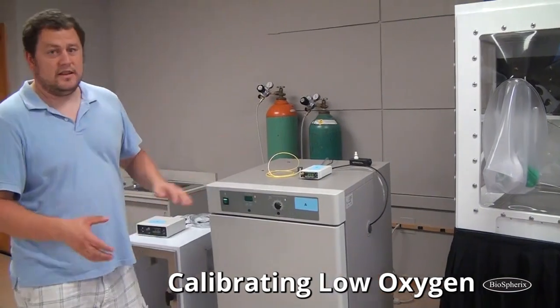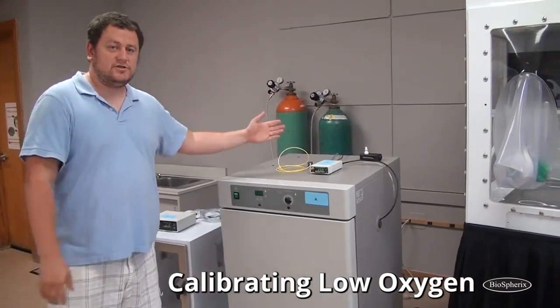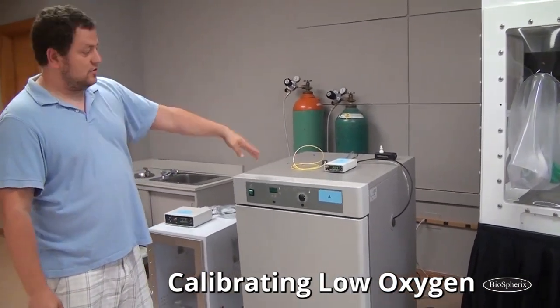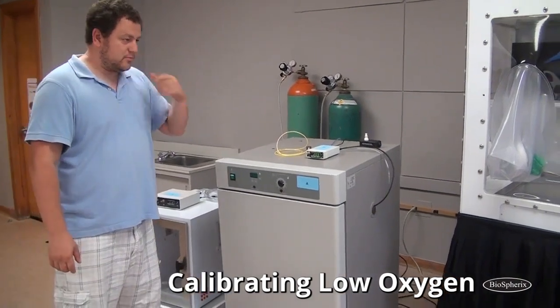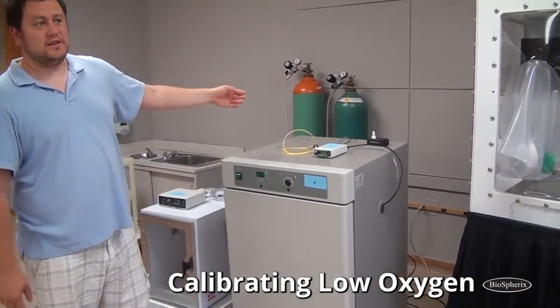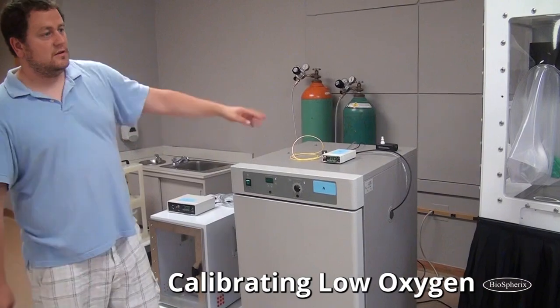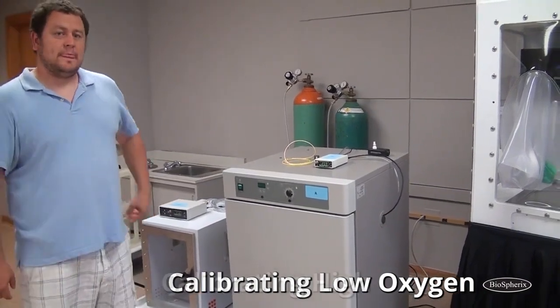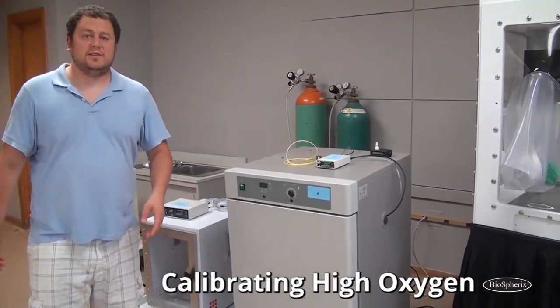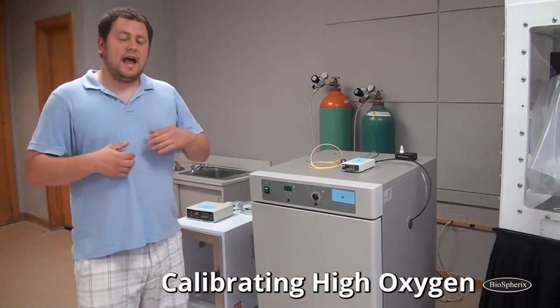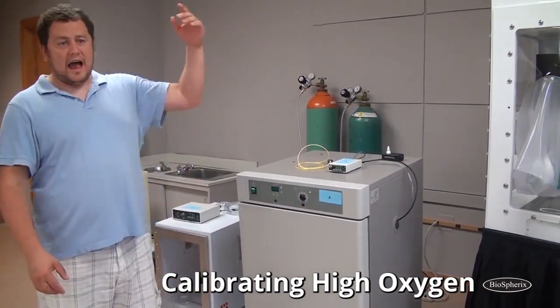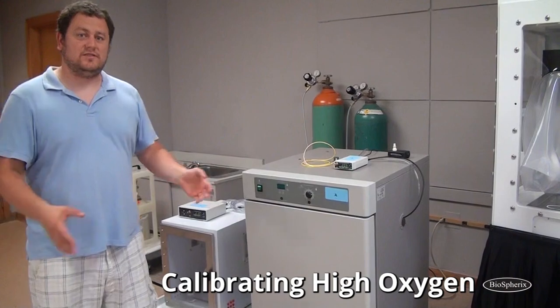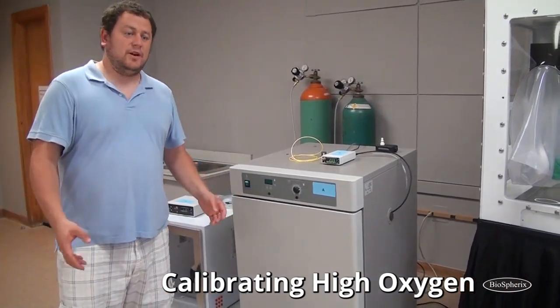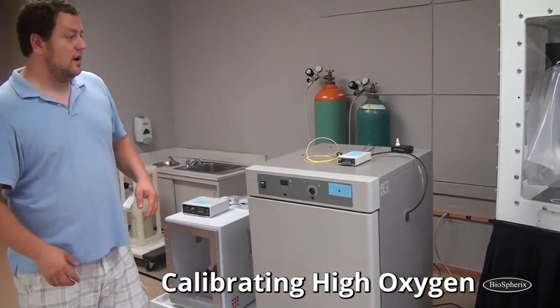So that's how to calibrate if you have a nitrogen hooked up to your ProOx 110 or your P360. Again, any of those works exactly the same. The manual also describes what to do if you have oxygen hooked up, if you're doing high oxygen work, because you don't have access to a 0 gas at that point. So I'm going to cover that as well.